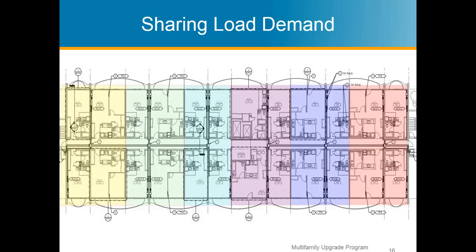So if you can throttle that down to the demand that it needs, if at the peak time it really only needs a half a ton, well, you don't want to put in a conventional 1.5 ton unit just to satisfy a half ton of load on a peak demand time of year. So in the height of summer, maybe it hits the need for a ton of cooling, or whatever the peak demand may be, but it's only say 2-3 weeks out of the year. The rest of the year it's pretty moderate, and it doesn't need all that. When it is kicked into cooling mode, it doesn't need 12,000 BTUs to satisfy the load.